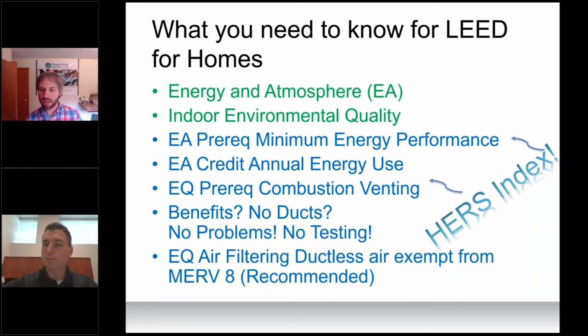And the other thing to know is that it's easier to meet the heat load calculation sizing goals with these types of systems. Sometimes what we're finding, especially in tighter, well-built homes or multifamily, is that traditional gas forced air systems are typically oversized and can't even qualify for the LEED or Energy Star program. So this is one easier way to get to it, and it connects right within that first prereq of minimum energy performance. All those things I mentioned are mentioned in there. And then, you also have to commission these systems, that Mike was referencing, but there's much less commissioning involved, especially when going ductless and when using radiant, way less commissioning than you have to do with forced air systems.